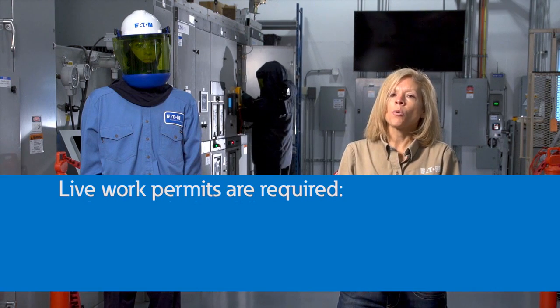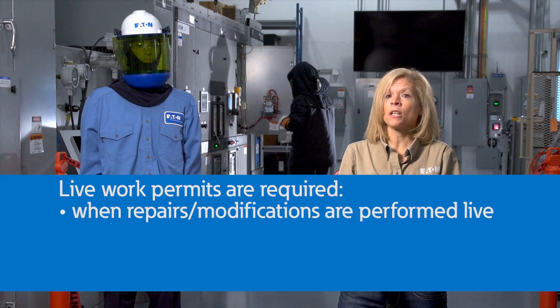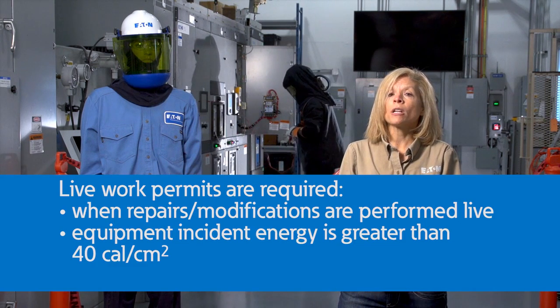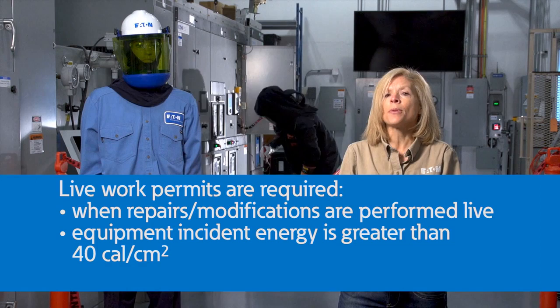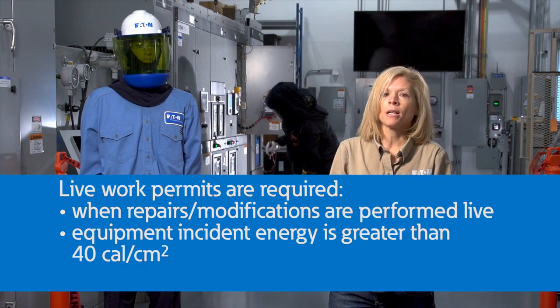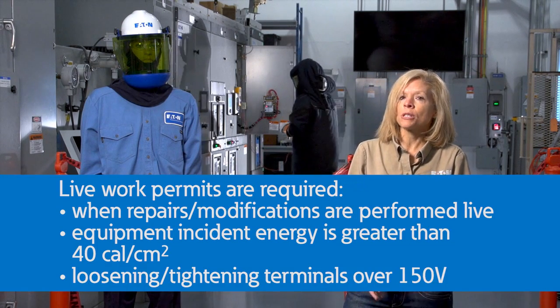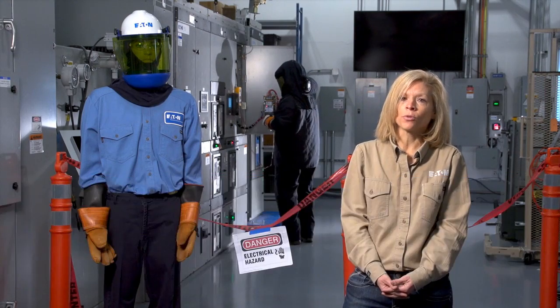Live work permits are required whenever repairs or modifications are performed live, or working on equipment where the incident energy is above 40 calories per centimeter squared. This also includes loosening or tightening terminals over 150 volts.